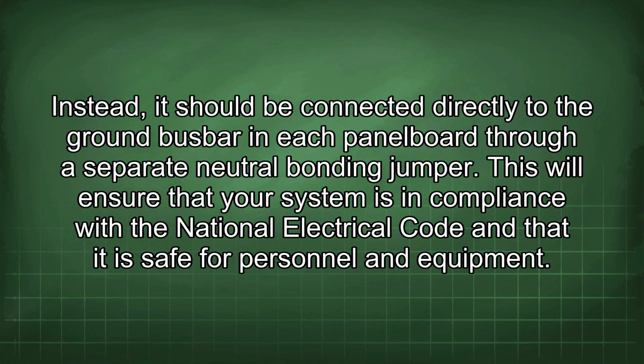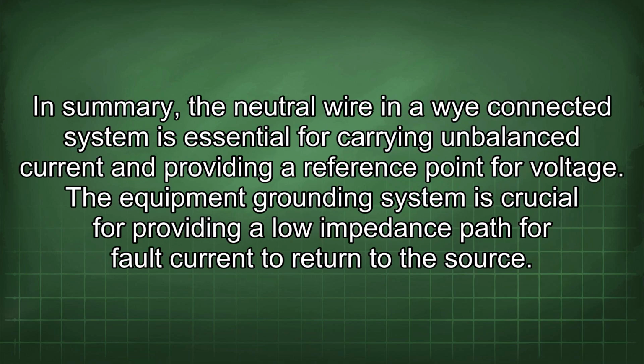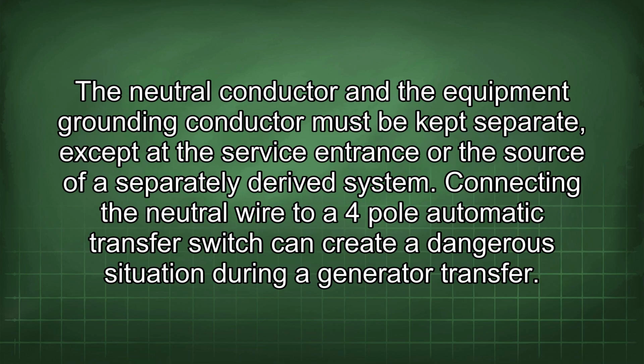This will ensure that your system is in compliance with the National Electrical Code and that it is safe for personnel and equipment. In summary, the neutral wire in a Y-connected system is essential for carrying unbalanced current and providing a reference point for voltage. The equipment grounding system is crucial for providing a low impedance path for fault current to return to the source. The neutral conductor and the equipment grounding conductor must be kept separate except at the service entrance or the source of a separately derived system.